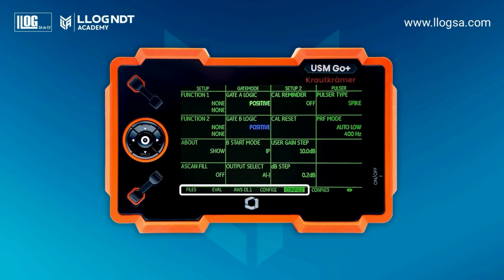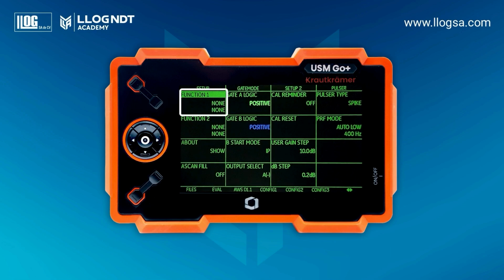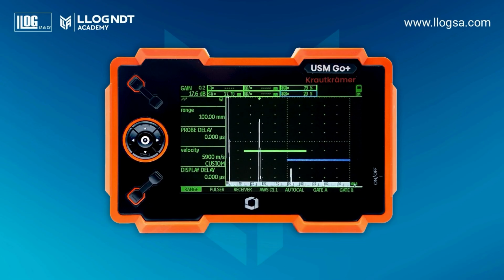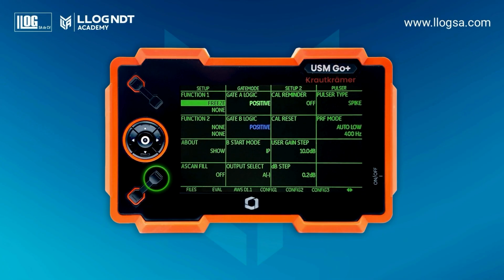The 5th group contains special configuration functions. Function keys 1 and 2 can be customized to activate quick functions. For example, if we assign Freeze Display to function key 1, when we return to the A-scan and press that key, the function will activate and the Freeze Display icon will appear in the top left corner. To unfreeze the display, simply press F1 again.